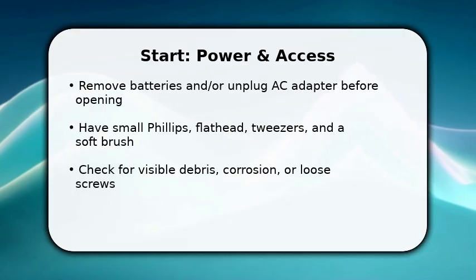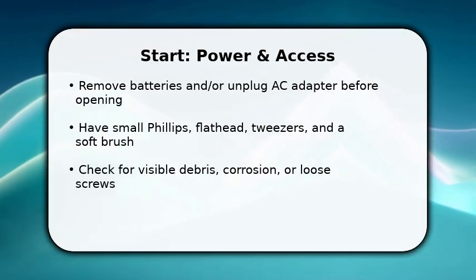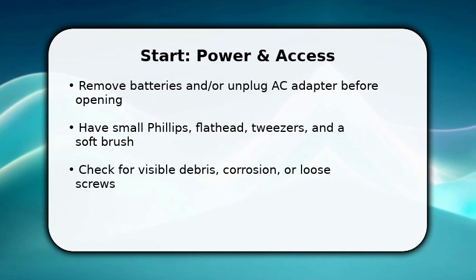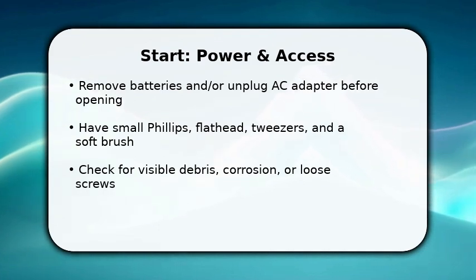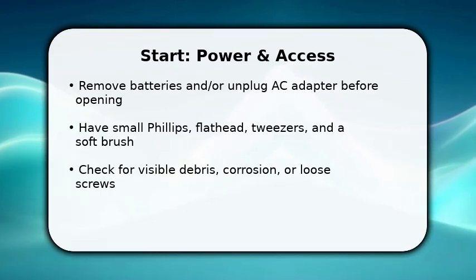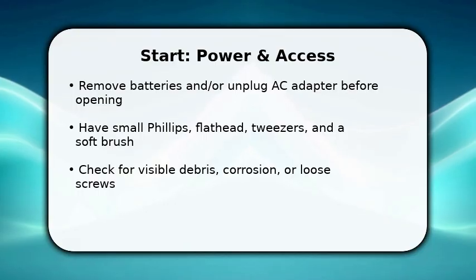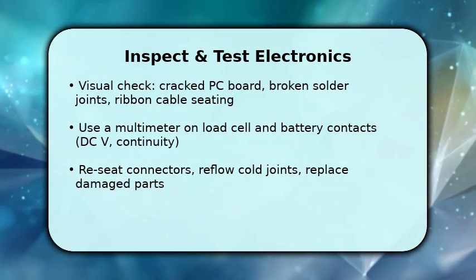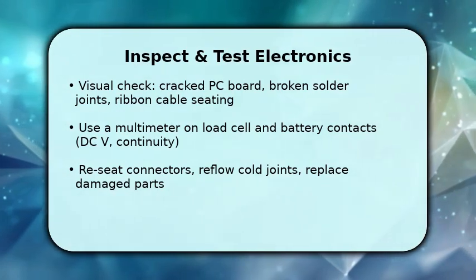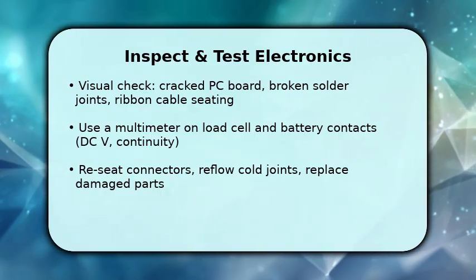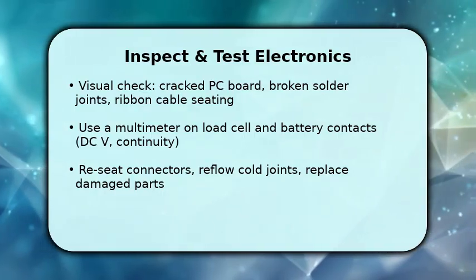If you see green or white corrosion at battery contacts, gently clean with a cotton swab and isopropyl alcohol to restore conductivity. Next, inspect the circuit board and load cell closely. You'll test continuity and voltage with a multimeter. Check battery contact voltage, then measure the load cell leads for continuity and expected resistance. This tells you if the sensor is open or shorted.